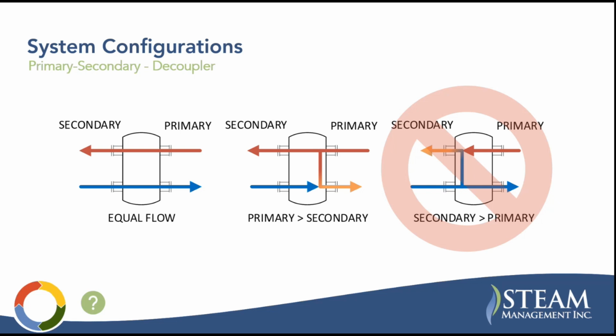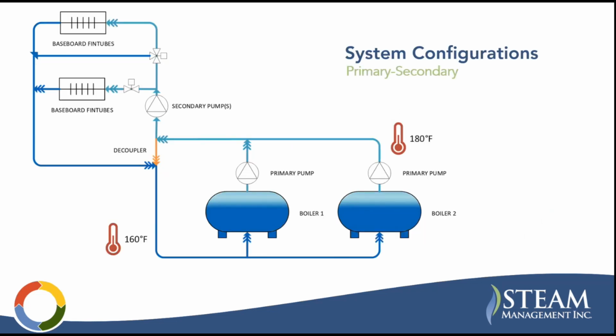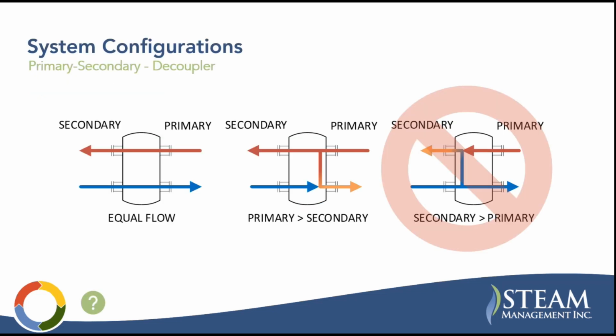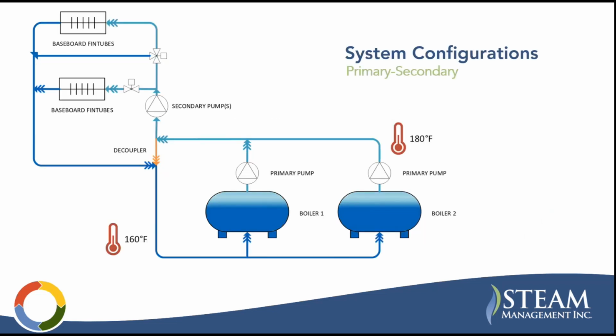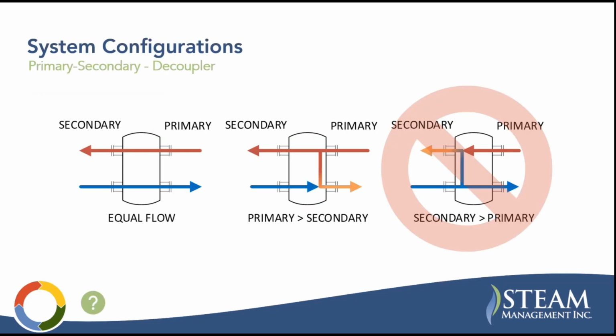Back to the decoupler, though, this is the concept of the decoupler. Again, we're talking about this orange path. If you have equal flow in your primary and secondary loops, basically your primary is going straight to your secondary and flowing right back into the return of your boilers, and you have no decoupler flow. So you would be going out of the boilers, straight from primary to secondary, all the way around and straight back into the boilers, with no flow here. That's ideal, right? That's not a real-world scenario most of the time.